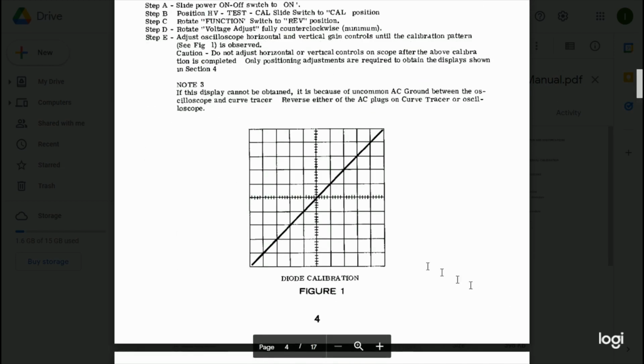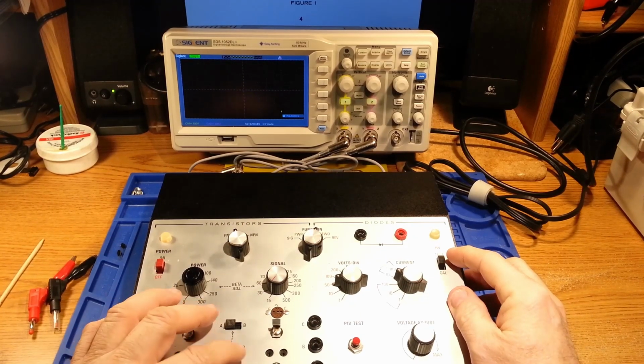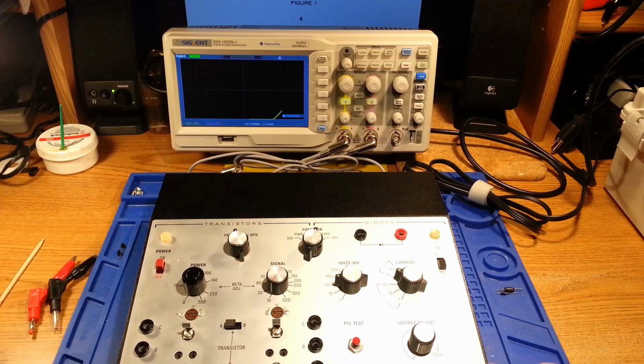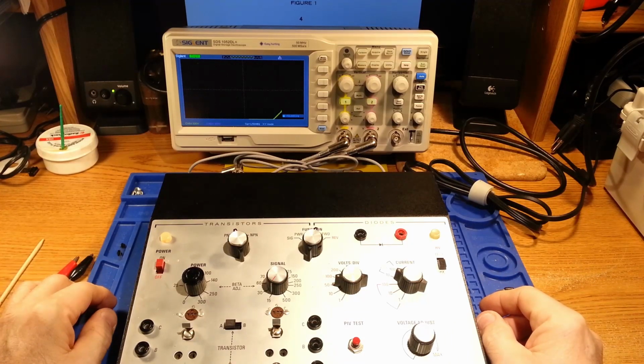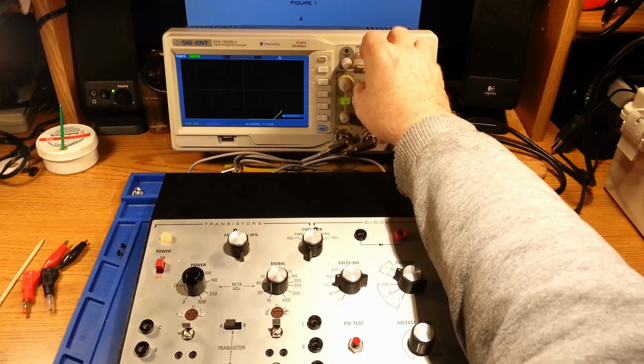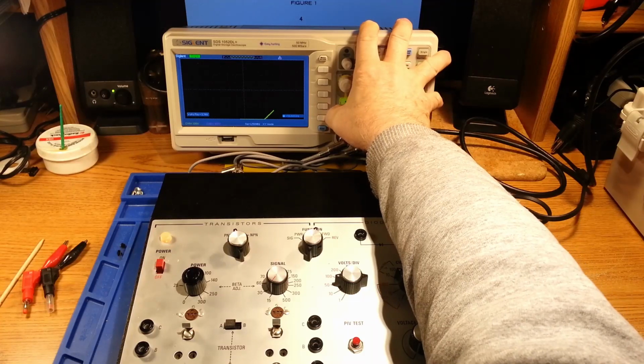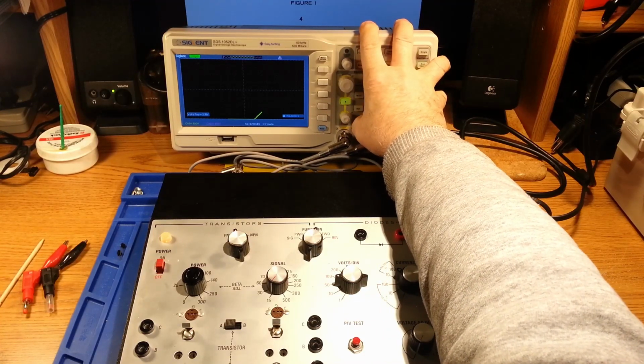So it's not necessarily going to calibrate properly, because part of the calibration is basically it wants you to set up the test signal so it gives a 5x5 or a 10x10 45-degree horizontal, and in this case I cannot do that. I am going to calibrate the scope as well as I can to get it to a proportionate display, but I won't be able to do a 10x10 in any way, shape, or means.